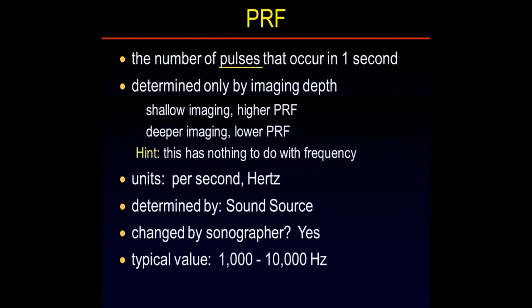Now, the number of pulses a machine sends out in 1 second ranges from 1,000 to 10,000 hertz. And there is a tendency to say, oh, 1,000 hertz to 10,000 hertz, that's audible sound. But we're not going to do that. No, no, no, this is the PRF. So that means the ultrasound machine is sending out between 1,000 to 10,000 pulses per second, but the frequency of sound making up the pulse, that's ultrasonic. And that's why we are so careful about describing the word hertz the way we do. Because we don't want to think that this has to do with the frequency of the transducer. It doesn't. What does this have to do with, and only with? How deep I image.